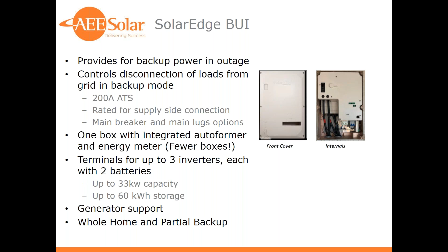So this is really the straw that stirs the drink with respect to this new platform: moving the relays and the interconnection out of the inverters and into the backup interface unit. And I say move the interconnection, and obviously the inverters are still going to have IEEE 1547 and UL 1741 protocols for de-energizing. Really, what I'm talking about here is the mechanical connections that will disconnect under load. Your inverter will still do that, obviously, but the backup interface unit is rated as an ATS, and it's capable of islanding everything downstream to create a larger microgrid than the 5 kVA rated SolarEdge inverters were before. So not enough credit to the electrical distribution equipment here, what we used to call big gray boxes, but now comes in a more aesthetically pleasing white cover with some metering and monitoring functionality as well.